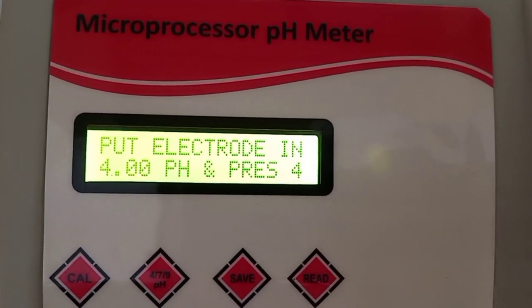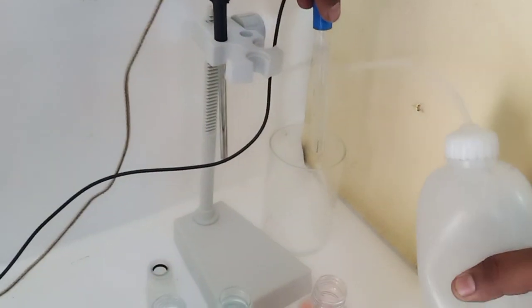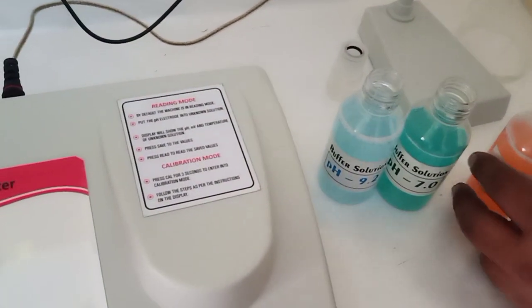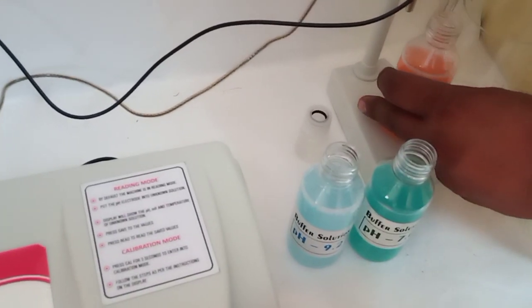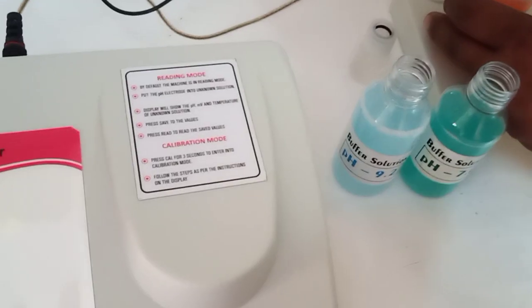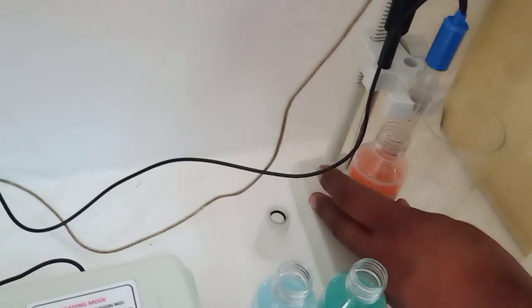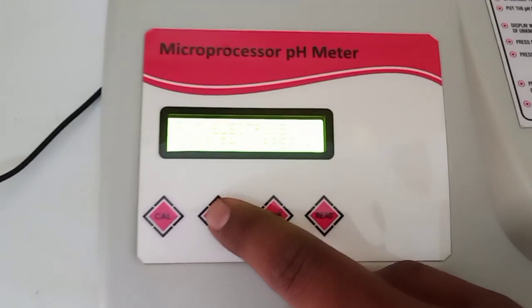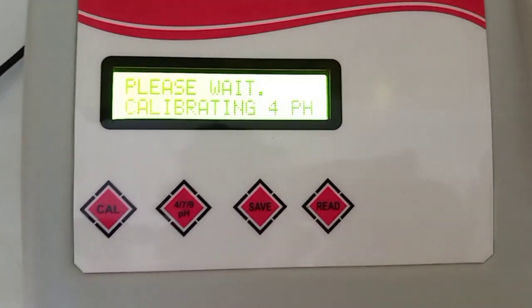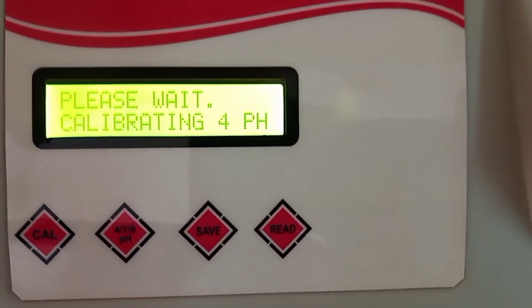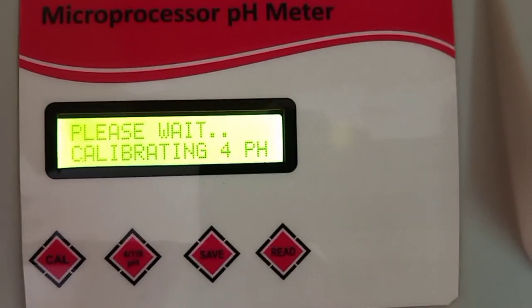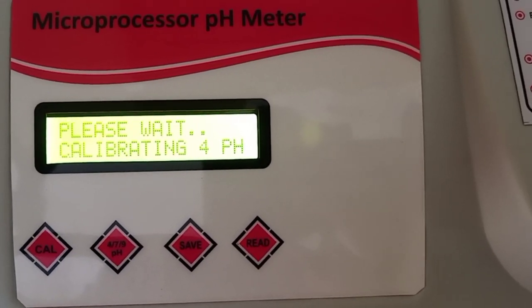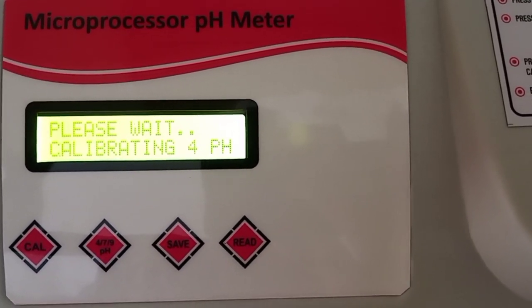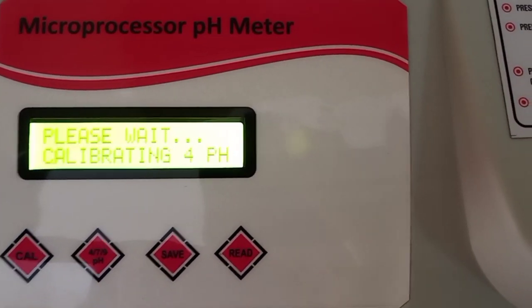Display showing put electrode into 4 pH and press 4. Properly wash the electrode with the distilled water. Put the electrode into the 4 pH buffer. And press 4. Display showing please wait. You have to wait for approximate 1 to 2 minutes for the calibration process. Once the calibration of 4 pH is over, display demands 7 pH buffer.